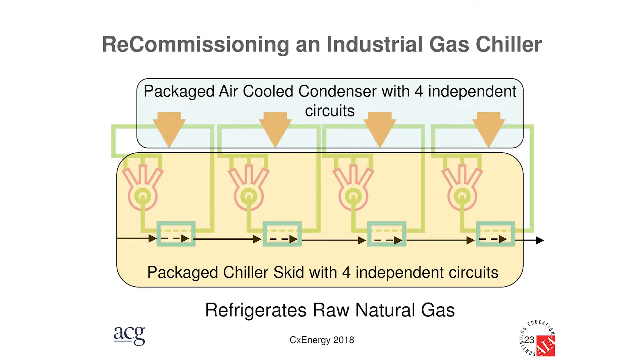So the package air-cooled condenser is one condenser outside with 4 refrigeration circuits in it. The skid has 4 compressors and 4 evaporators in it. And the natural gas sequentially goes through them in series, so it gets colder and colder as it goes. There's one more heat exchanger on this, one more evaporator. That's an economizer evaporator, so they take the chilled natural gas and cross it with the incoming gas, and it pre-cools the incoming gas.